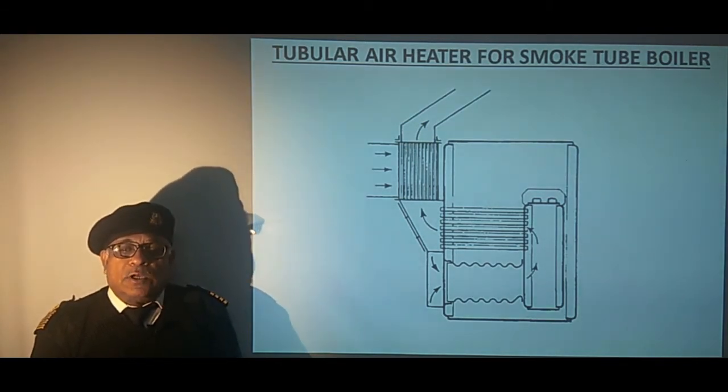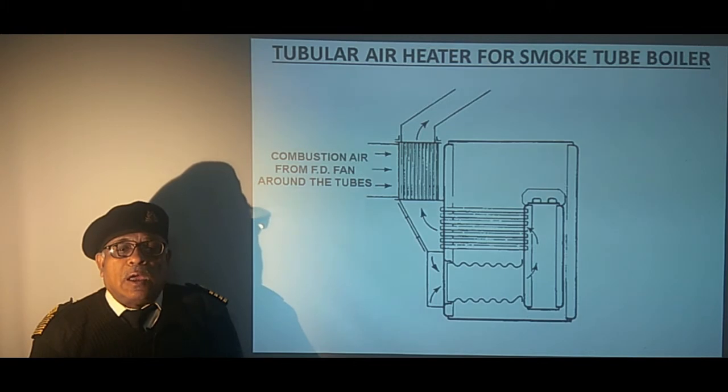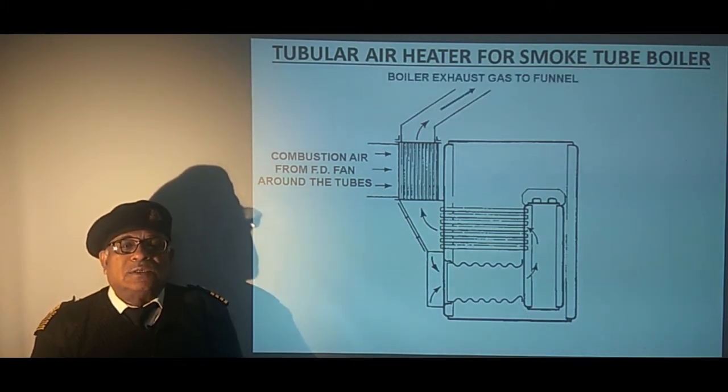Air after passing around the smoke tubes enter the air register through plenum whereas flue gas after heating the air leaves through the funnel which we can see in the sketch. Combustion air from FD fan around the tubes takes away the heat from the flue gases which are passing in the tubes and the exhaust gases coming out from the air heater leave the boiler and go to the funnel.